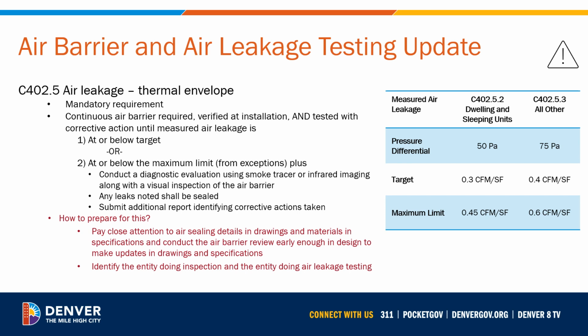Code sections covering air barriers and air leakage testing have been updated in the 2022 Denver Energy Code. This mandatory provision requires continuous air barriers, verification at installation, and testing of building air leakage. Air leakage testing has been modified in the 2022 code to now require the measured air leakage to be at or below a CFM per square foot target.